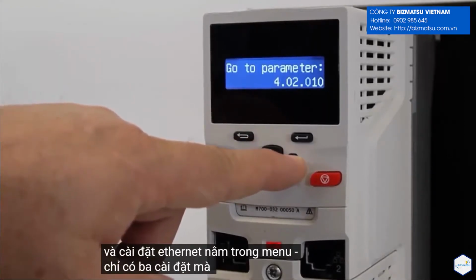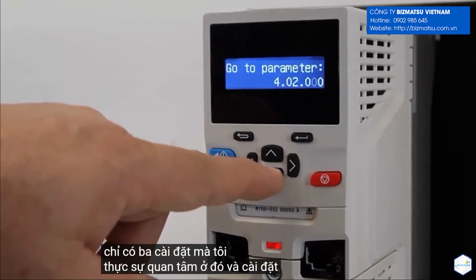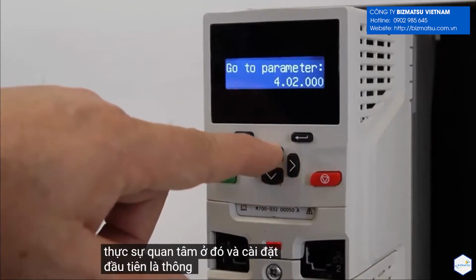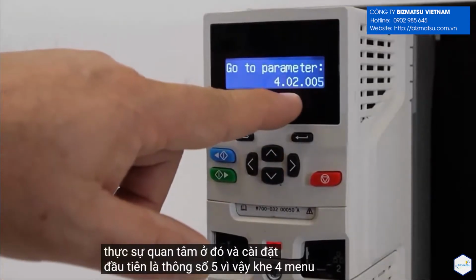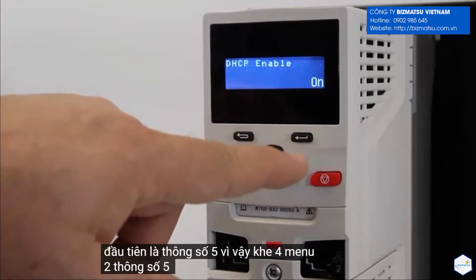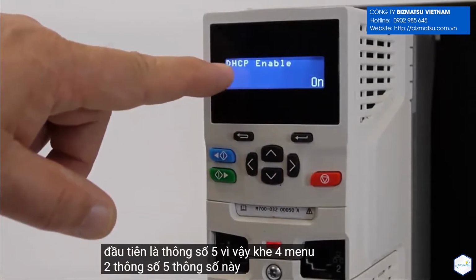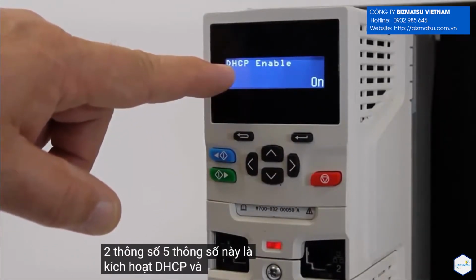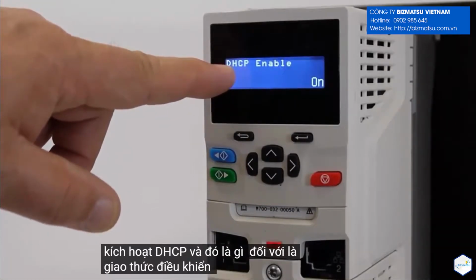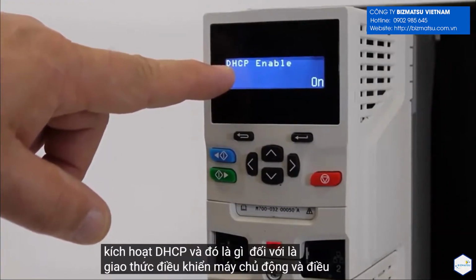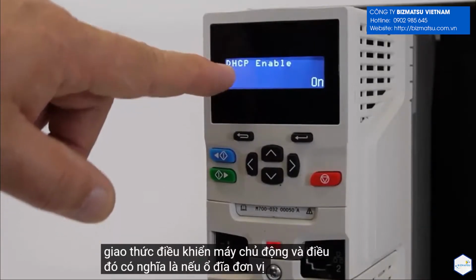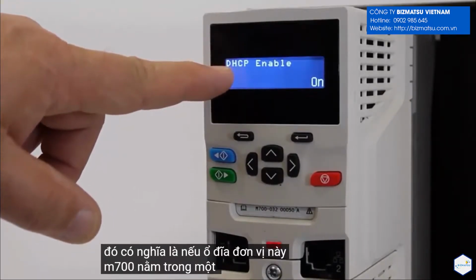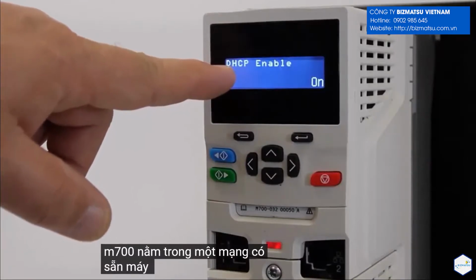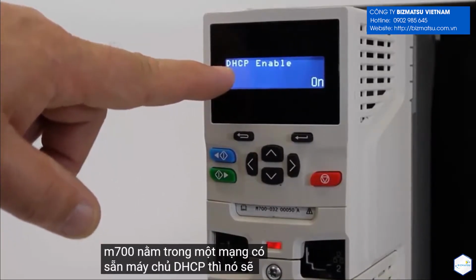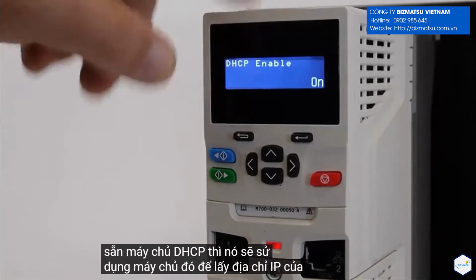Slot 4, and the Ethernet settings are in menu 2. There's only 3 settings that I'm really concerned with there. And the first one is parameter 5. So slot 4, menu 2, parameter 5. This parameter is DHCP enable, and what that stands for is Dynamic Host Configuration Protocol. And what that means is that if this Unidrive M700 were in a network that had a DHCP server available to it, then it would use that server to obtain its IP address.